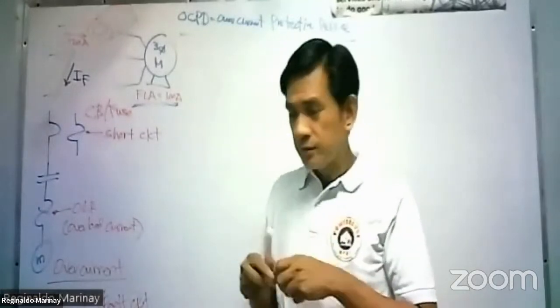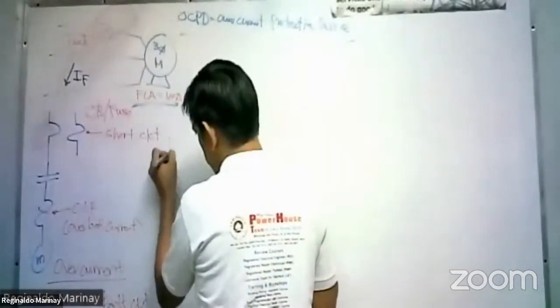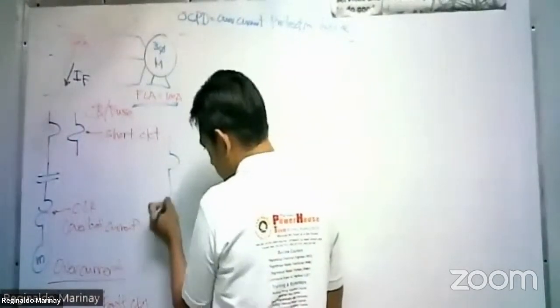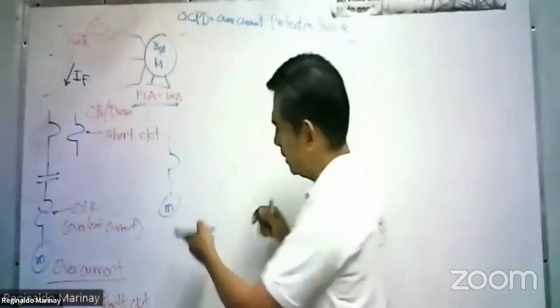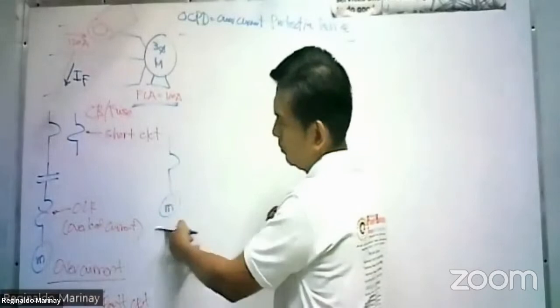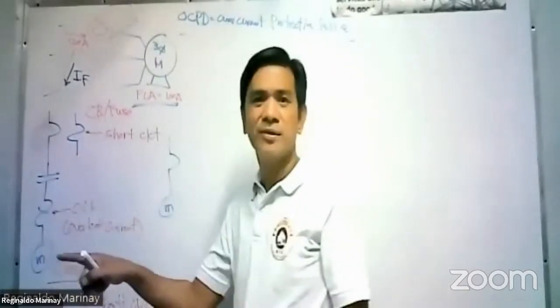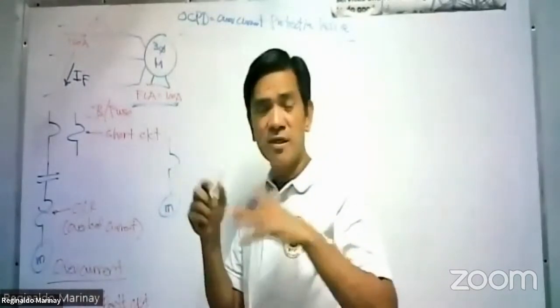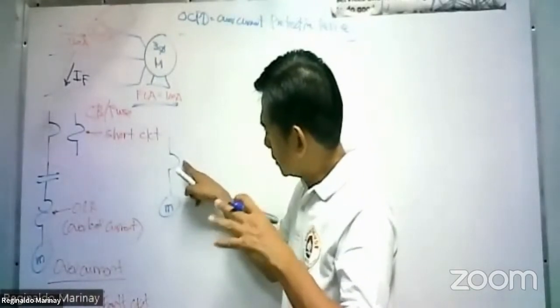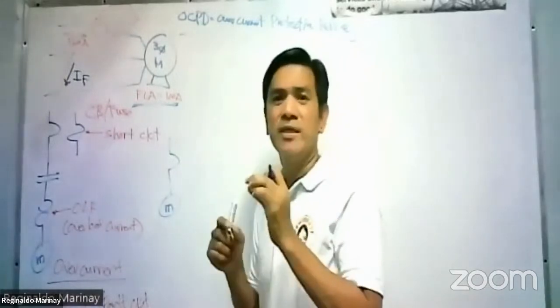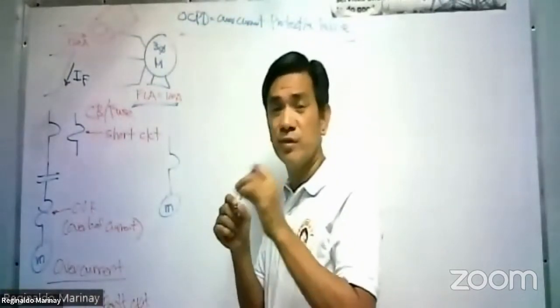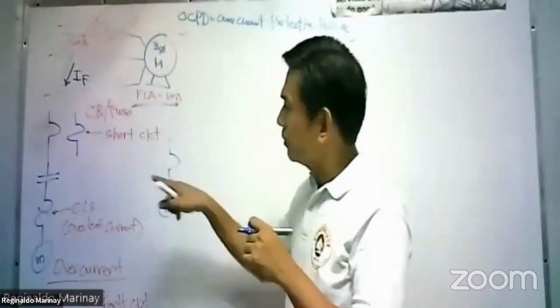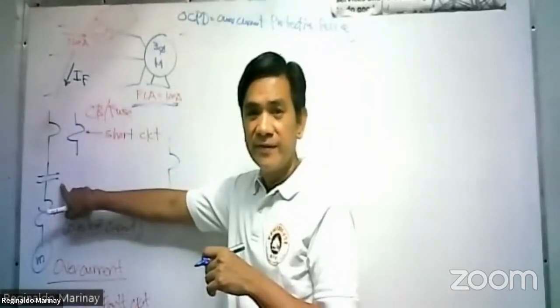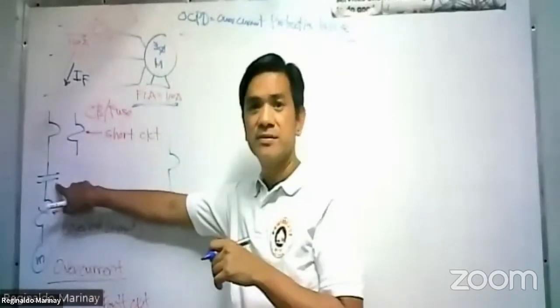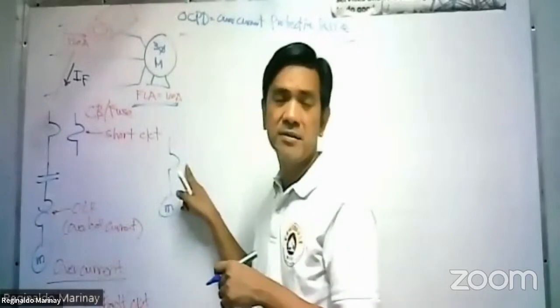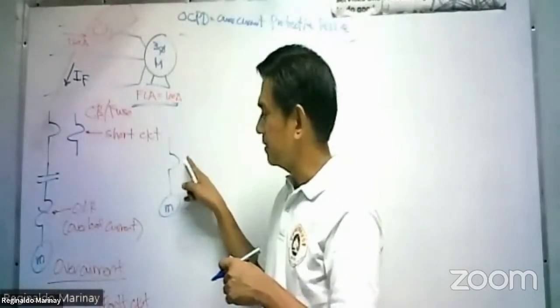So if we have here the motor, sometimes there is a circuit breaker, then motor agad. You will see a motor here. There is no overload relay, there is no magnetic contactor. Because basically, especially in the smaller horsepower of this motor, the circuit breaker is also a switch actually. You don't have a push button, the circuit breaker may act also as a switch. Meaning the function of the magnetic contactor, as a switch, is taken by the circuit breaker.